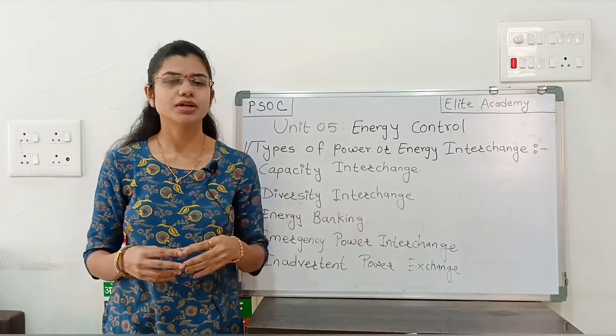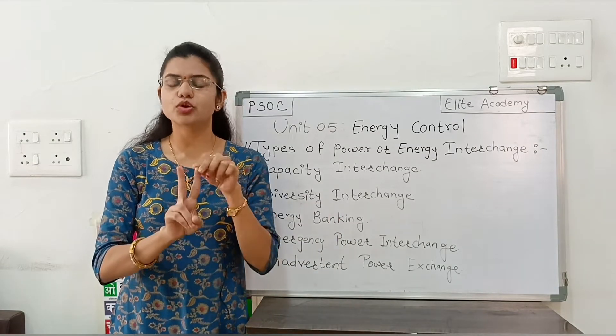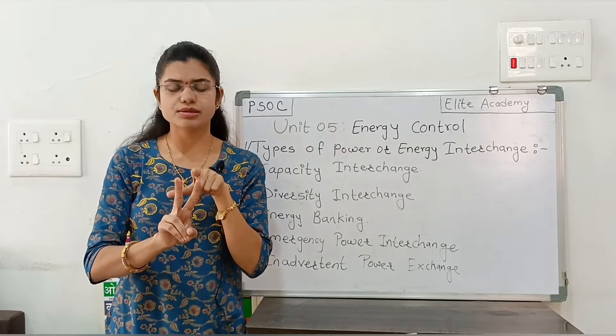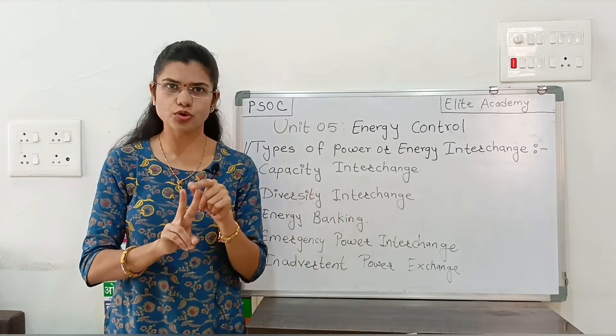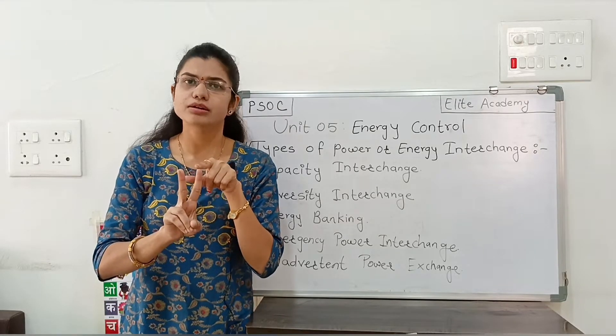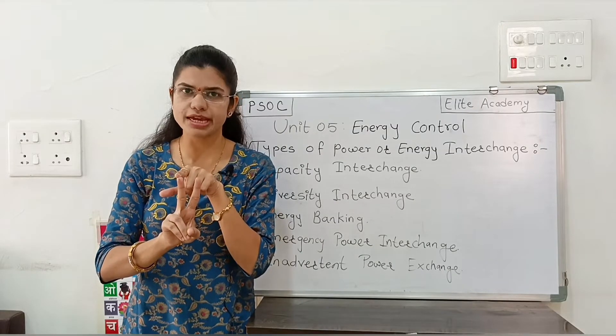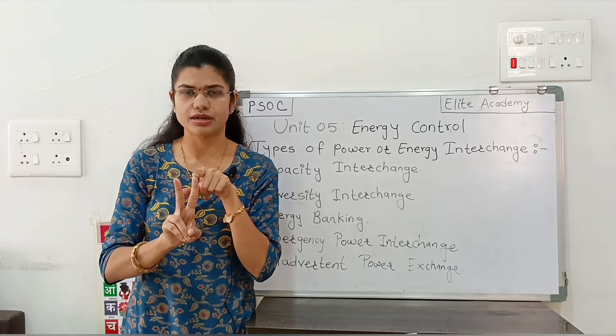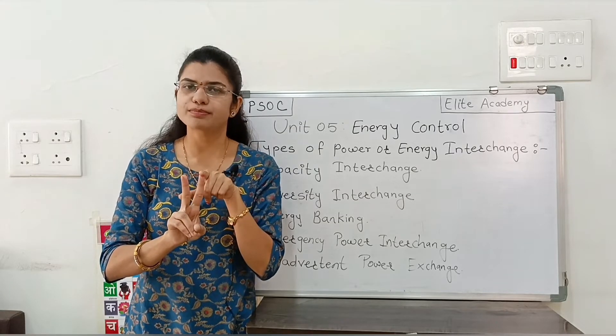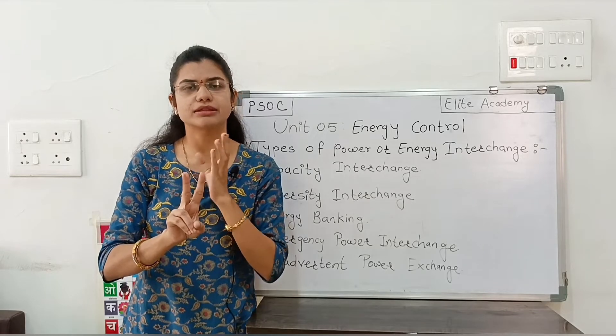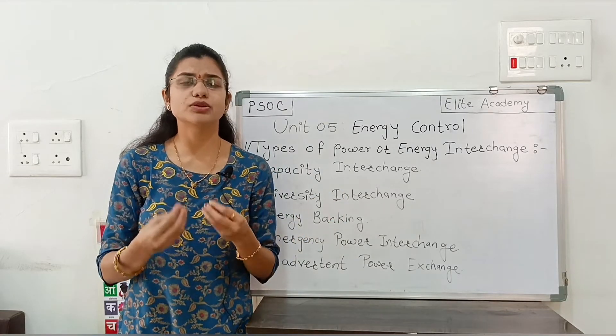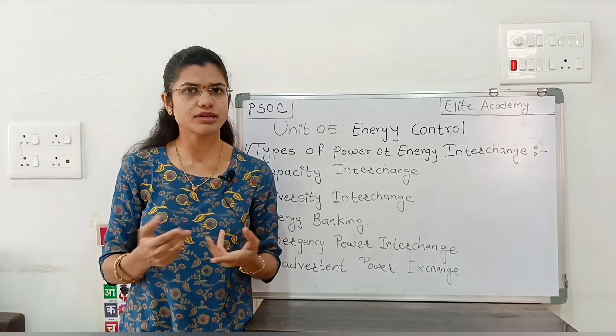The second type is diversity interchange. This is the interchange between plants in different time zones where two plants have different peak load time periods. Suppose one plant's peak load time period is one hour before the second plant's. The first plant will buy some energy from the second plant during its peak load time period. This interchange can also be possible during different seasons.